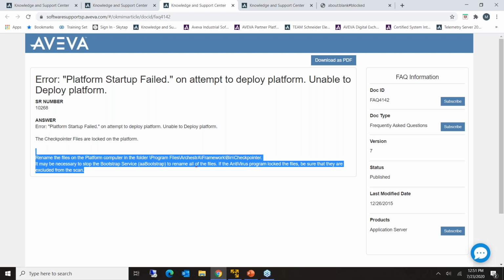So you have to make a backup. You can export and import all the objects, but as I said, for example, if you have a script library or third-party script or anything you are using inside, it's not part of the object, it will not be exported. Only the object and the related things will be exported with it, the graphics, but not everything. In case you want to export the whole galaxy, it is better to export the whole galaxy as an entity, so do the backup restore part.